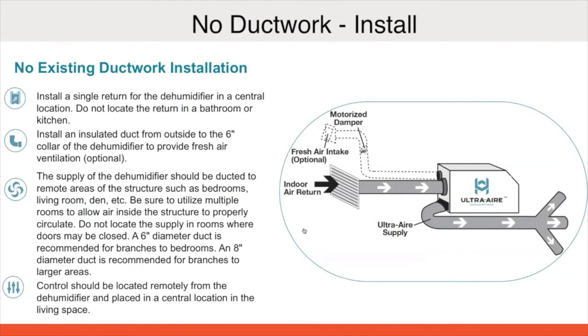No ductwork. A lot of times we are the ventilation, air mixing, air distribution, and dehumidification in ductless mini split applications. So we have homes that will install a dehumidifier with some minimal ductwork. The key on this one is off that supply to make sure that you have typically about three areas of supply where we're delivering that air, because again, dehumidifiers do create some warm air, and we want to make sure that we're getting that dry air throughout the whole house. Plus, if you're using us for ventilation, we want to be distributing that ventilation air as well.